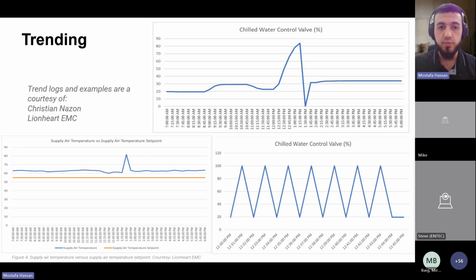So this is a trend log. There's a couple of trend logs that I'm going to show here, but all of these are from an air handling unit that typically in this specific scenario works in tandem with a chilled water control valve, right, to supply a specific supply temperature to the space. Now, a couple of disclaimers: the sequence of operation has to be checked properly to confirm the enabling and disabling conditions for temperature control and operation.